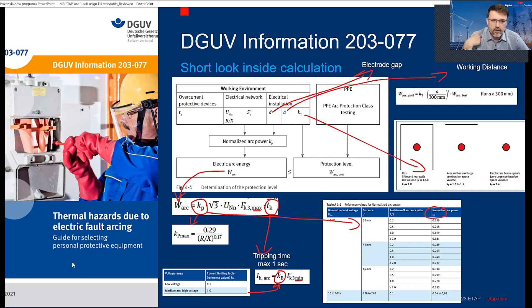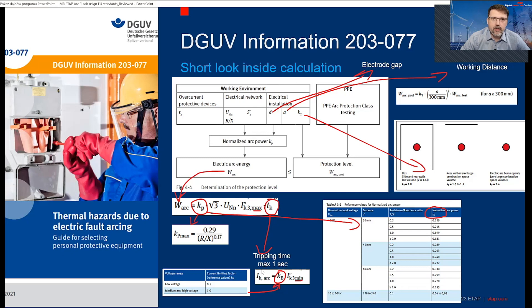Let's have a look at DGUV itself. This documentation you can download from their website. If you look inside, it's a relatively simple calculation. The calculation for arc energy includes the KP factor, voltage, three-phase maximum short circuit current, and time — which is limited to one second. Tripping time is based on the minimum short circuit current and the KB factor. KB is the factor making the arcing current: 50% for low voltage, and 1.0 for medium voltage and above.